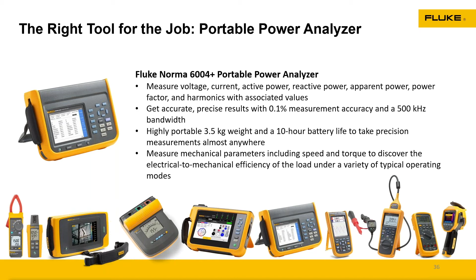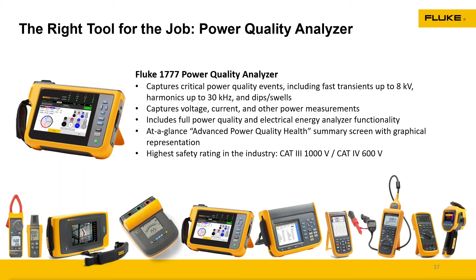Even on the 1777, a power quality unit is going to allow you to make sure, like on what I mentioned earlier about that site in Georgia where the utility was causing the tripping aspect, having a good power quality meter on the AC side is going to allow you to analyze if you've got good voltage, no unbalance of voltage and current coming out of your inverter, and also determine if there are any additional harmonics or anything else coming from the utility side that might trip that system.